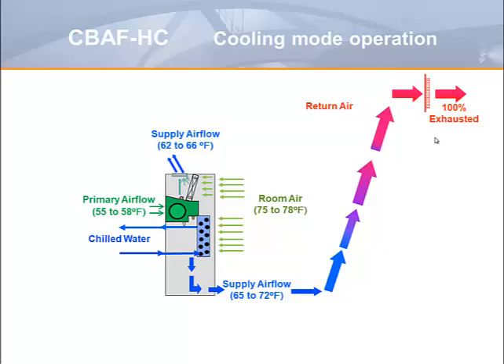Most classrooms can be adequately conditioned and dehumidified with a primary airflow delivery equal to or just slightly above the required space ventilation rate. Most applications allow the chilled water supply to be maintained at least 1 degree above the space dew point temperature so that no condensation to the terminal unit occurs. Note that the return airflow from the classroom is equal to the primary airflow rate so that the return air is exhausted and no recirculation at the air handling is necessary. As such, the recycling of airborne contaminants to the classroom served by the air handling unit does not occur.